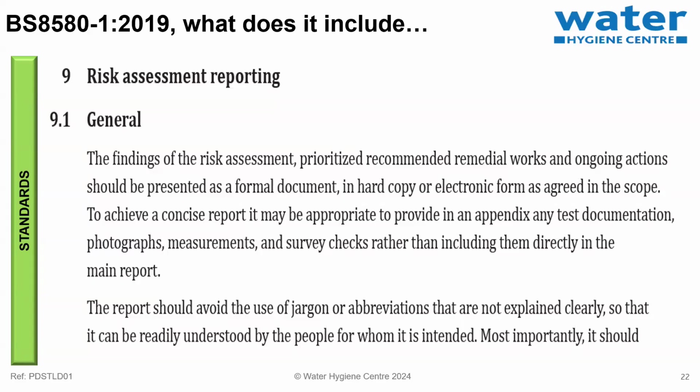A risk assessment should be clear and concise, should have an action plan, the risk minimisation scheme, and needs to include a priority status for the recommendations, and the deadlines for the prioritised actions need to be agreed by the responsible person or the water safety group. How can a risk assessor determine deadlines for an organisation if they don't control the budget?